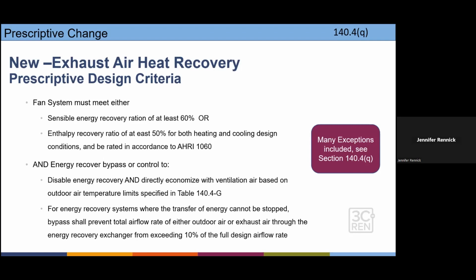And heat recovery, for those of you who are not understanding that term, it means that as an airstream, say, leaving the building is filled with warm air being exhausted out of the building, the incoming cold air, let's say we're in heating mode, can go through, not mingle directly, but touch through a thin membrane that warm air and transfer the heat into the cold air. So now the cold air is tempered. It's not as cold, and you're introducing that to the building, and that warm air that you were exhausting has now been cooled off because its energy has been transferred into the supply air, and it leaves the building, thereby saving energy. But if the fans use too much energy in and of themselves, it's not a net gain of energy savings.